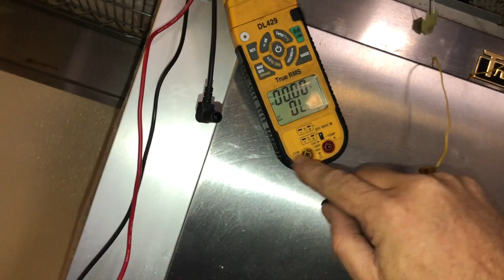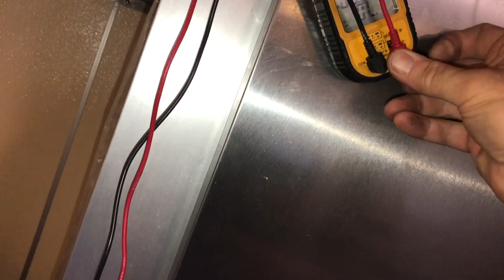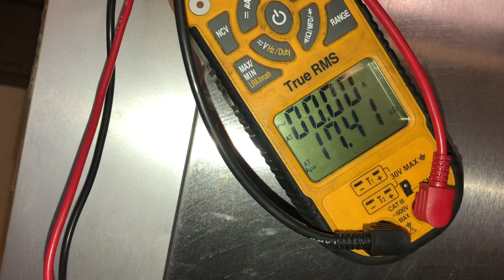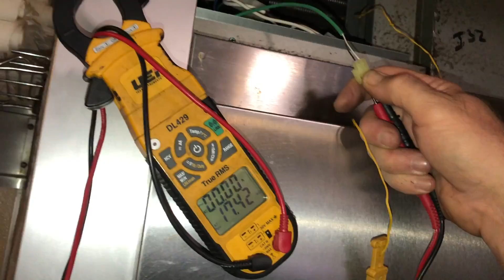To get an ohms reading, you got to take the temperature out, flip the switch up, put your leads back in, and go to K ohms. I might have to put the camera down to put these in real quick, and then we'll get the reading. It's reading 17.4 K ohms. Let's go find the chart on my phone, I know I got it in the memory bank somewhere. 36 degrees, 17 - probably should write that down.